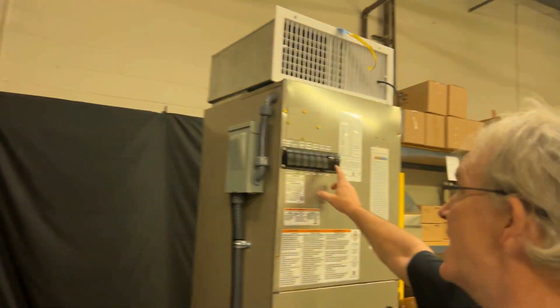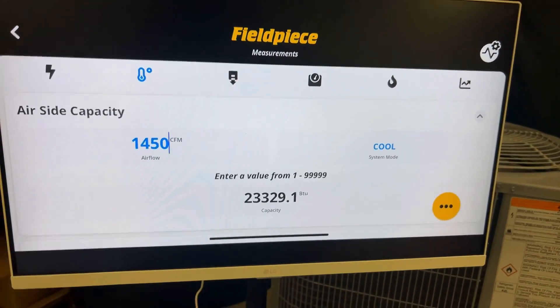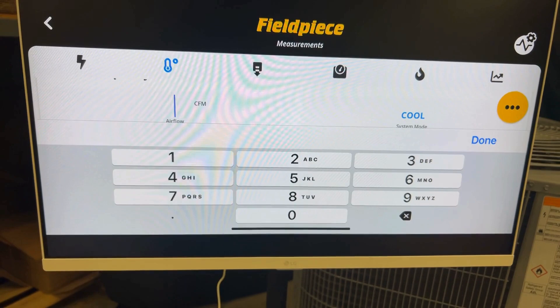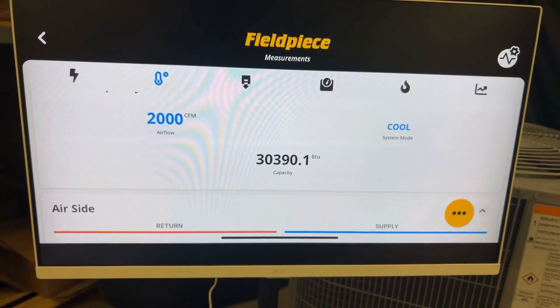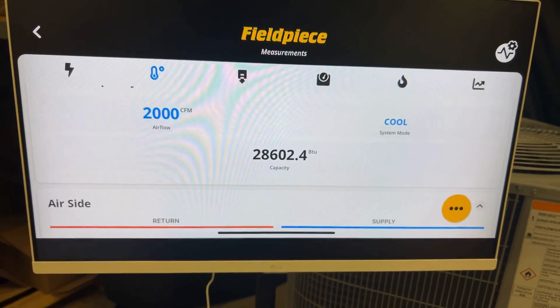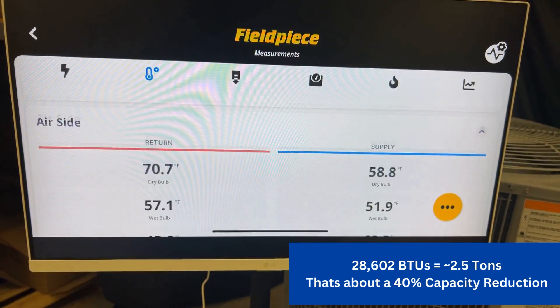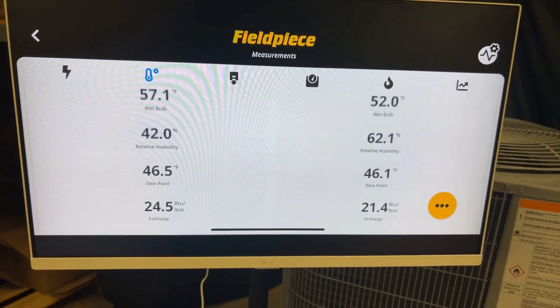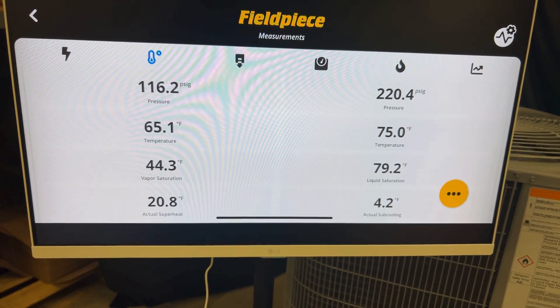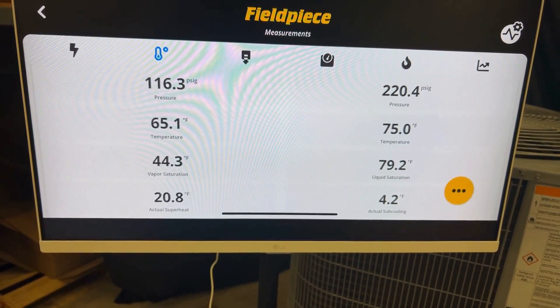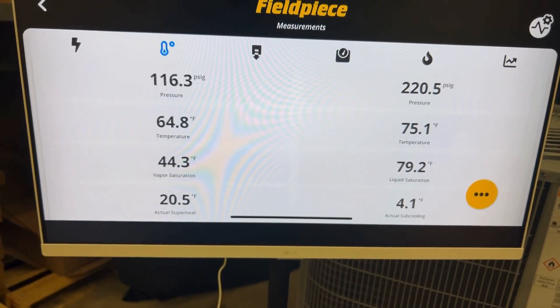Now let's turn it up to maximum speed on this four-ton unit, which is 2000 CFM as measured by our hot wire. Notice our capacity significantly increasing — let it settle down, it should increase a bit more. But even during all three phases of those fan speeds — the low profiles — we're still maintaining our suction pressure at 116, our superheat at 20, and our saturated suction temperature still remaining at around 44 to 45 degrees.